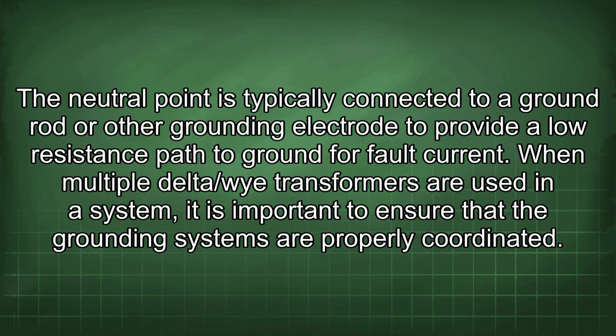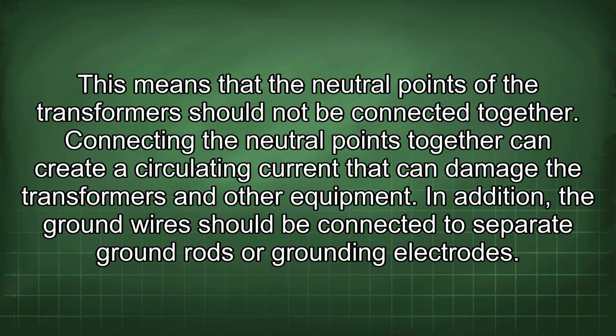The neutral point is typically connected to a ground rod or other grounding electrode to provide a low resistance path to ground for fault current. When multiple delta/Y transformers are used in a system, it is important to ensure that the grounding systems are properly coordinated. This means that the neutral points of the transformers should not be connected together. Connecting the neutral points together can create a circulating current that can damage the transformers and other equipment.